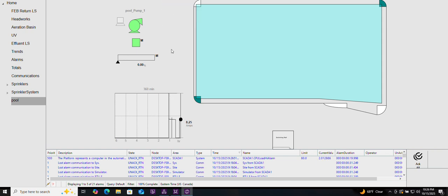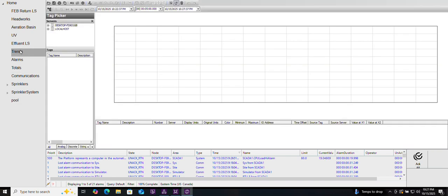We can change our date range. So I've got that off screen because I'm not showing them off screen. And there's your sparkline trend. You can't really do a whole lot with it other than change the time or reconfigure it for the sparkline trend. And these live in the real-time trend area, which I'm not 100% sure comes from the same source as your historian, if you have it pointed. I believe these trends just run for shorter periods of time in RAM, and then they're overwritten. To do a longer trend, we're going to need the SQL database.